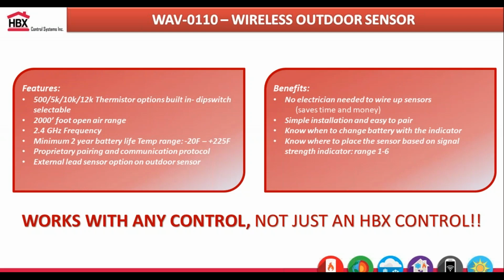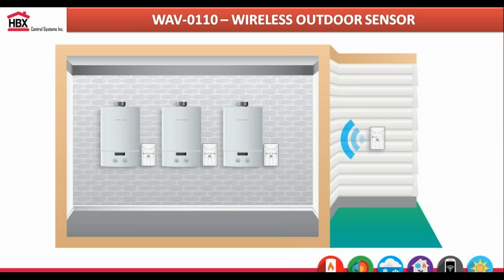The nice advantage to this is that it's low voltage. You don't need an electrician. It's just 24 volts to power up that base unit. Another option we give you with the wireless outdoor sensor is that you can pair up to 5 base units to 1 outdoor sensor. If you had 2, 3, or 4 boilers, you're not going to have a whole bank of outdoor sensors outside. You could pair 5 individual units to 1 outdoor sensor.